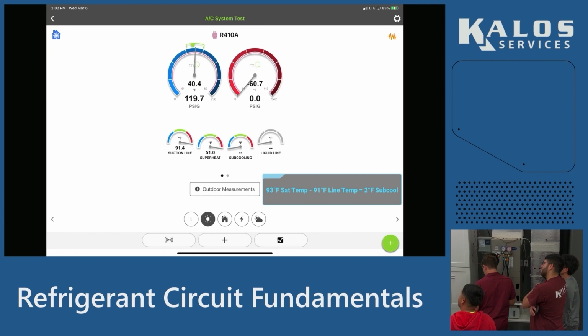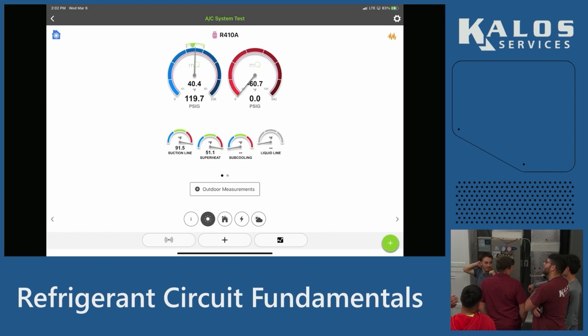Yeah. Well done. A little bit of experience would have told you that you're never going to have a liquid line colder than outdoor temperature, because it's the outdoor air that cools off the refrigerant.